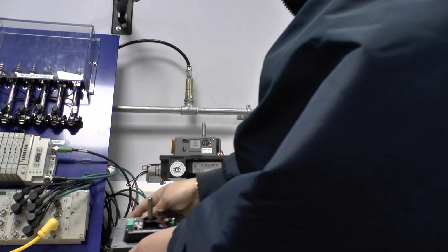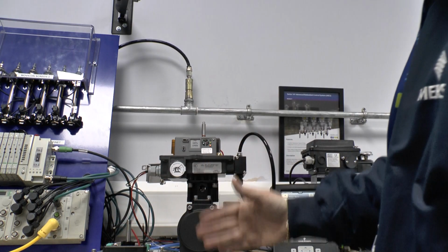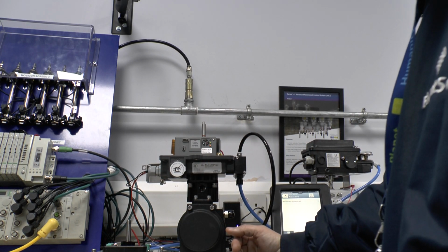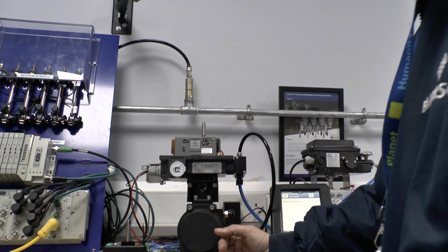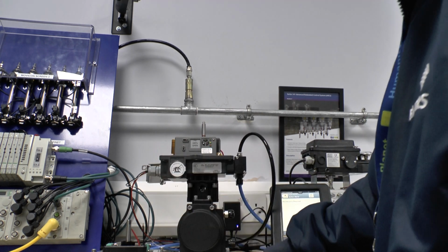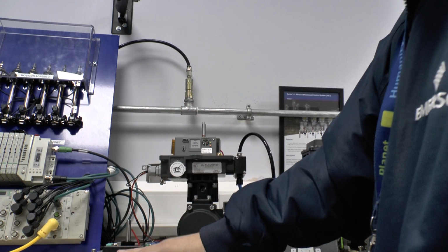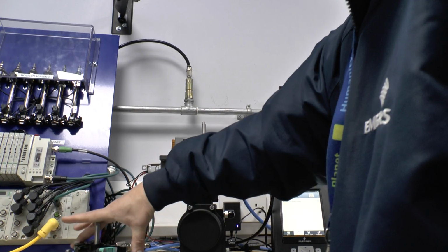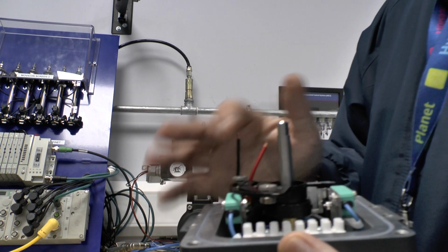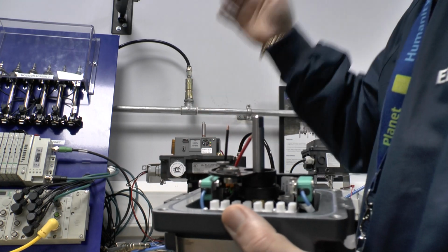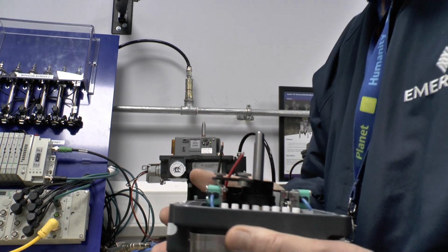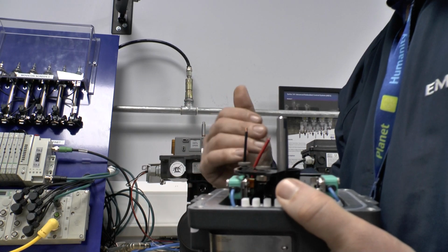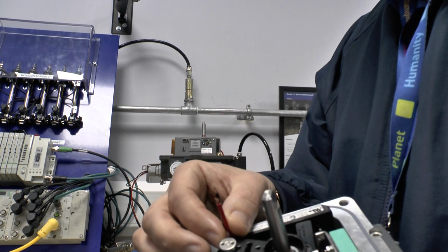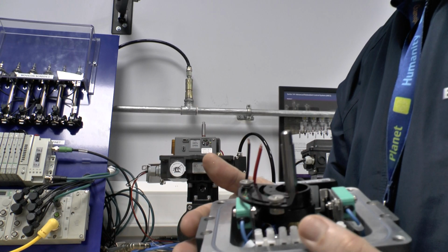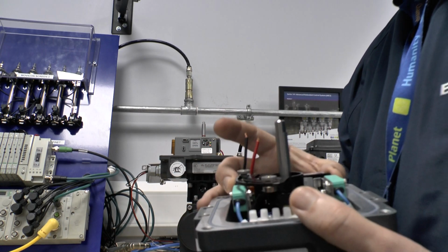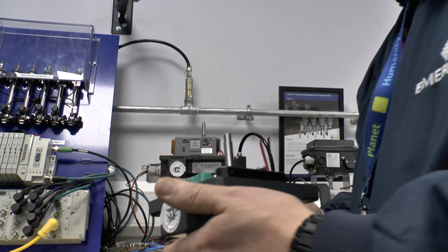What we say to customers is that a lot of times people are looking to upgrade or future-proof their plant just by simply changing a standard Switchbox to a Hart-enabled Switchbox. You still have the standard features in terms of being able to use normal switches, P&F switches, micro switches, Go switches to give your feedback. But when your plant becomes Hart enabled, it's just a connection of these two wires, and that creates the diagnostic features of the Hart to be utilised within your plant.